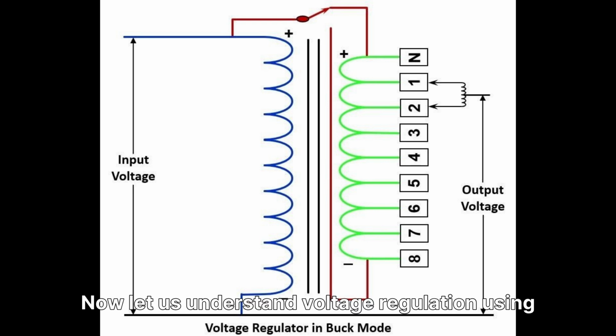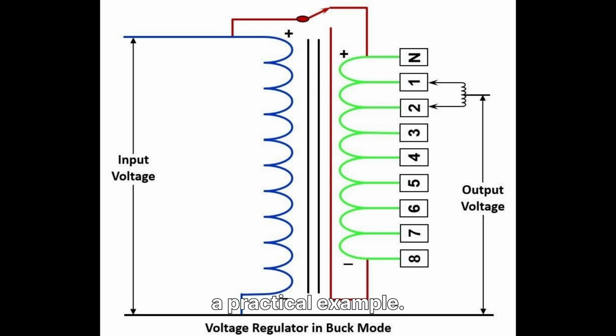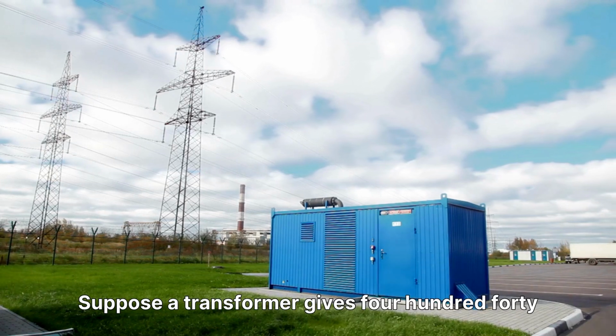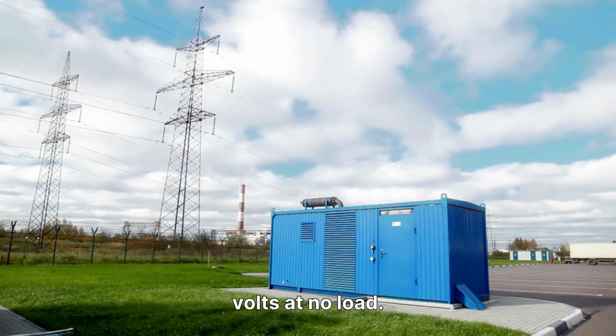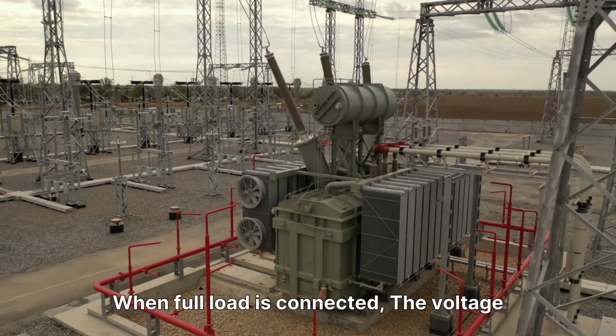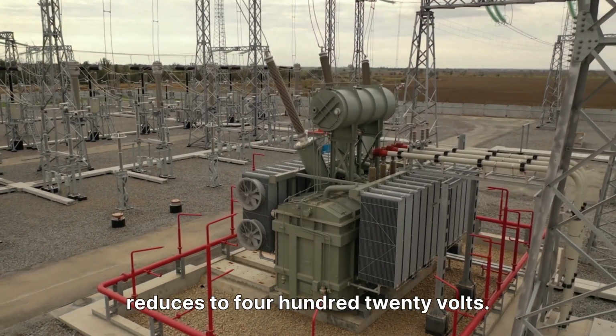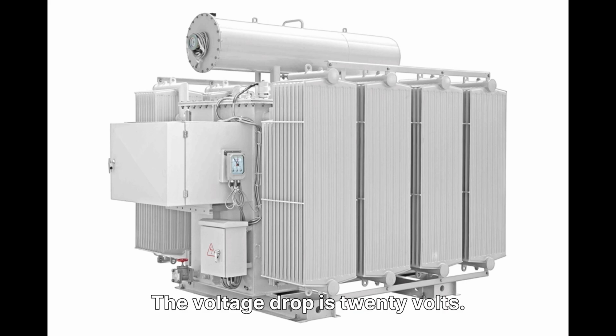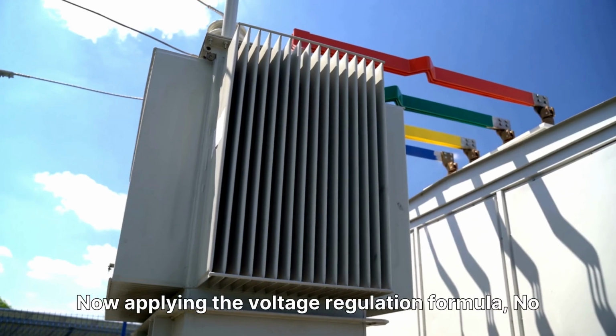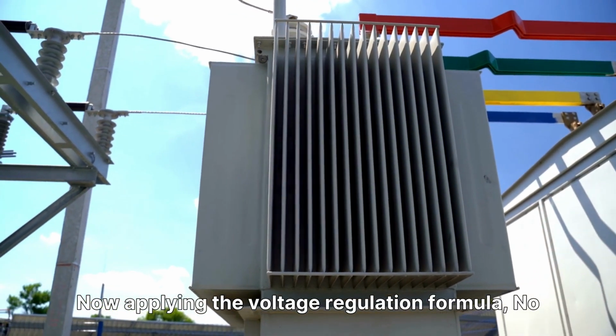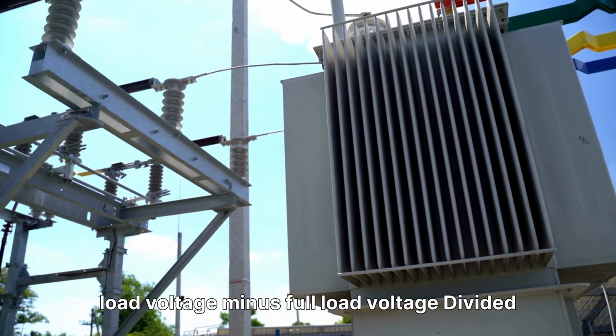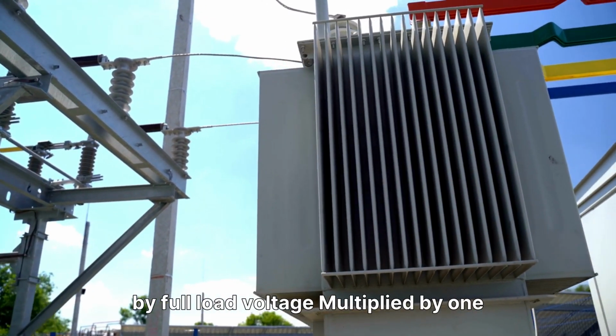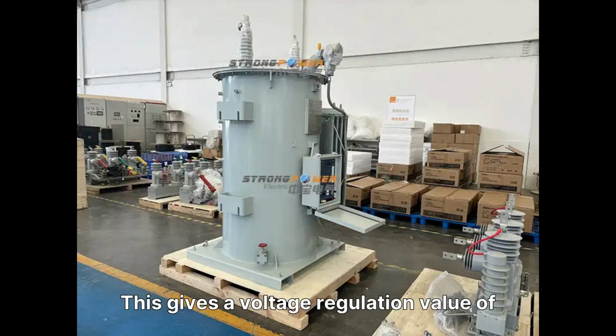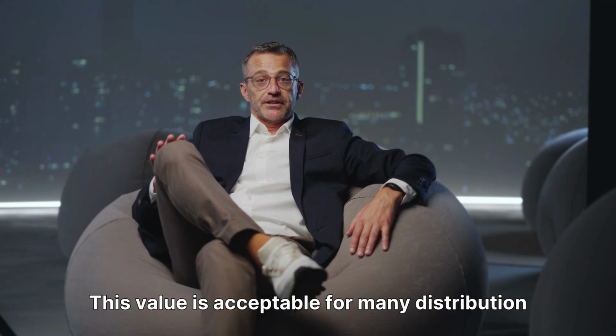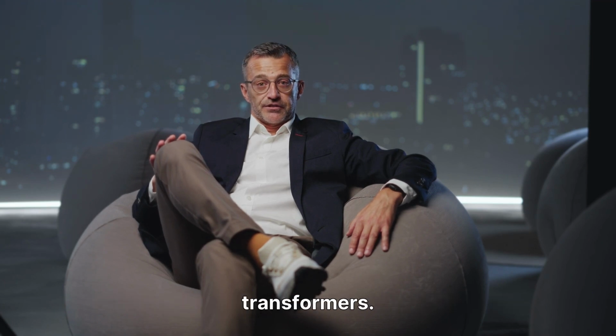Now let us understand voltage regulation using a practical example. Suppose a transformer gives 440 volts at no load. When full load is connected, the voltage reduces to 420 volts. The voltage drop is 20 volts. Now applying the voltage regulation formula: no load voltage minus full load voltage, divided by full load voltage, multiplied by 100. This gives a voltage regulation value of around 5%. This value is acceptable for many distribution transformers.